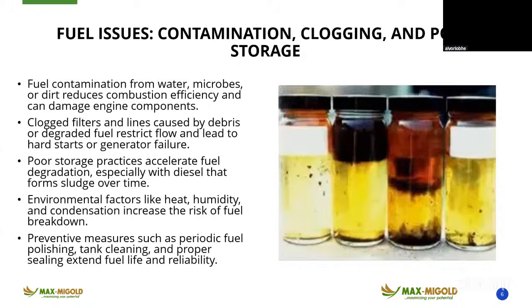Preventive measures such as periodic fuel polishing. That is, if you use a galvanized tank, ensure the inside is coated on a regular basis. If the part of your PPM can be every 2 years, every 3 years, you recoat the inside of your storage tank so that it will have little effect on the diesel. Also, you wash, you clean, you wash and dry on a regular basis. It should be part of your PPM. If you don't have it as part of it, ensure you put it there so that you are saving cost for your organization and also preventing generator breakdown. So proper sealing extends fuel life and reliability.